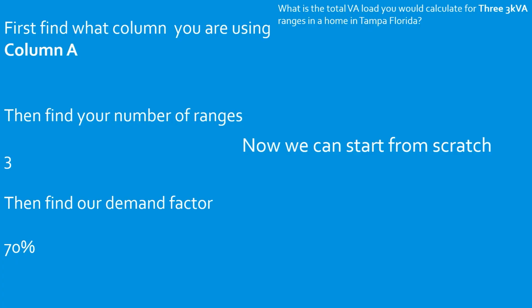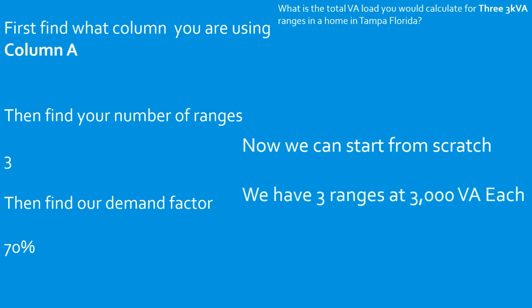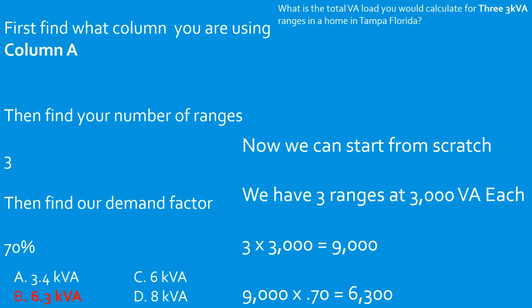And this is where you have to be careful because you have to first get the total demand and then apply the demand factor. So we have 3 ranges at 3,000 VAs each. So we take 3 multiplied by 3,000, that's going to give us 9,000 VAs. Now we apply our demand factor. We take that 9,000, we multiply it by 0.70, and that's going to give us a new total demand of 6,300 VAs. And we're going to select B.